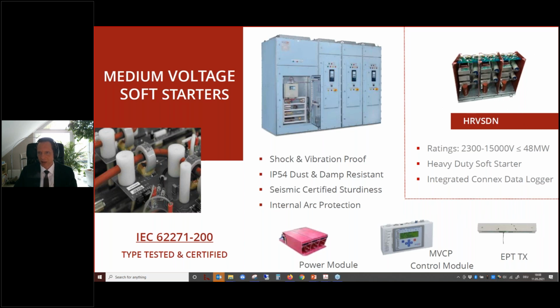Here you see, again, the power chassis with the thyristors as a cutout, and the ratings for these classic soft starters, I would call them, go from 2.3 up to 15 kV in voltage, and we can do up to 48 megawatt for starting motors of that size. It's for heavy duty, and they also have a data logger integrated, which is part of our offering.